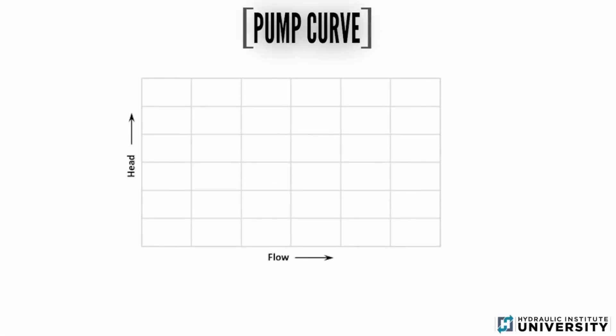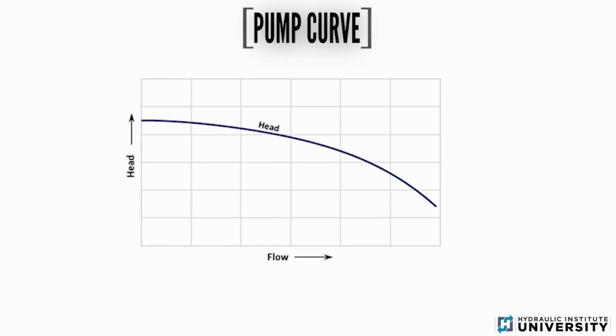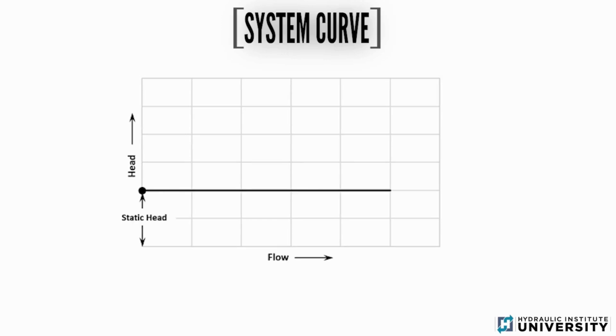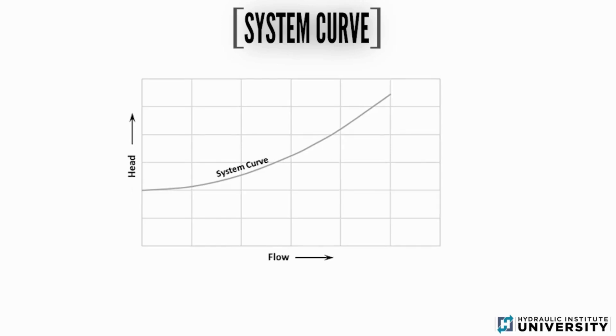A pump's hydraulic performance is graphically represented by pump performance curves. The pump head versus flow curve in particular is a valuable tool for understanding the pump's performance characteristics. The system curve is a graphical representation of head versus flow requirements of the system. It includes static head, which is not affected by flow rate, and increasing frictional head losses within the pump system at different flow rates.